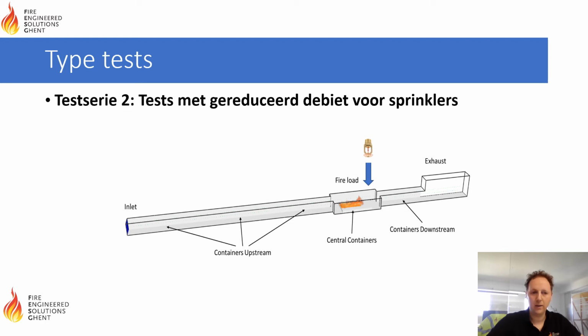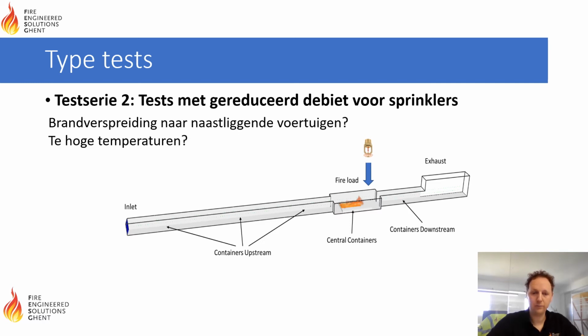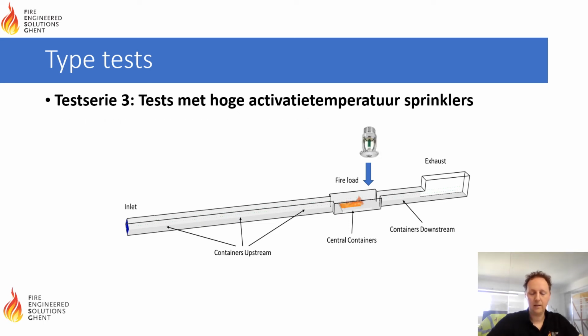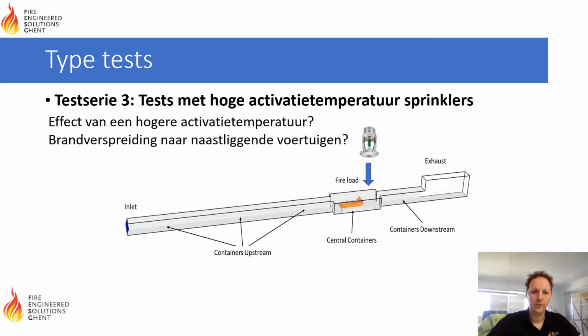Second series of tests was to do tests with a reduced flow rate for the sprinklers, looking if we would witness fire spread to adjacent vehicles or not. And then the third type of tests were with higher activation temperature of the sprinklers, and then look at potential fire spread.